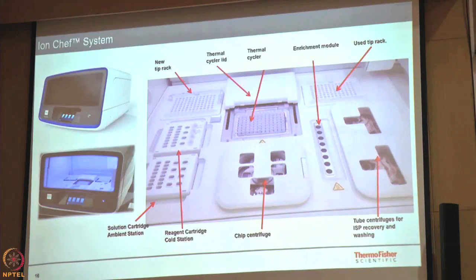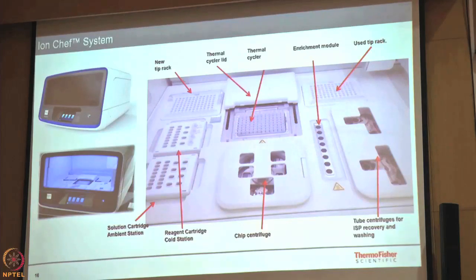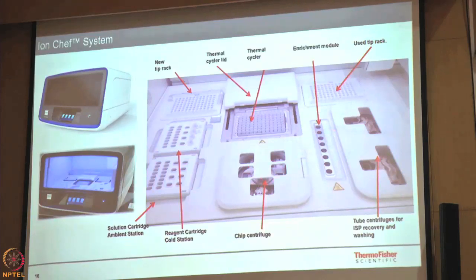When preparing libraries using the Ion Chef system, you load DNA samples and various cartridges into different sections of the system, and you get a final library pool in one of the tubes. For template preparation on Ion Chef, you again load cartridges and the system performs emulsification and amplification in a 96-well plate. Enrichment happens through a cartridge, then the centrifuge step loads chips automatically, and these chips are ready to go directly onto the sequencer.